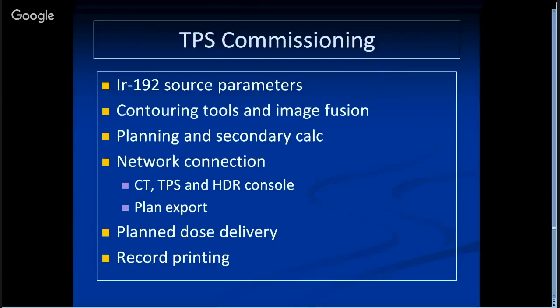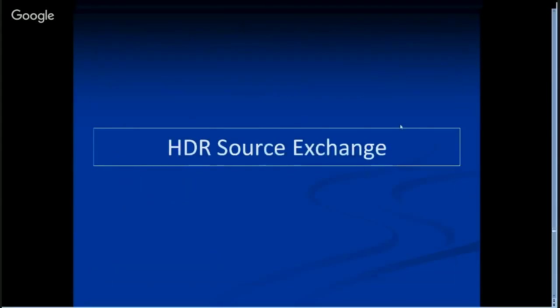For treatment planning system commissioning, you also need to do some geometry measurements. You scan a phantom, like 30 by 30 by 30, get the CT reconstruction dimension, and send that image to your treatment planning system. You compare the CT reconstructed dimension with the real dimension you measured, and the dimension from your planning system should be consistent with both.